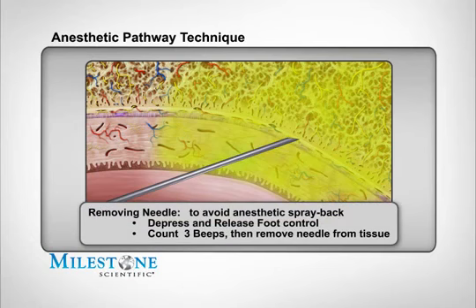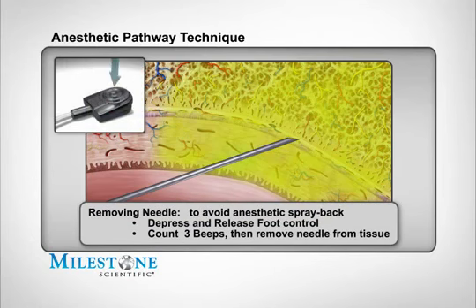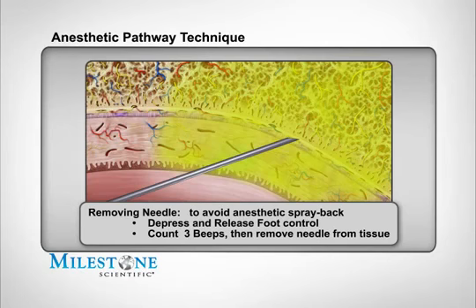To avoid anesthetic solution spray back into the patient's mouth, perform the following: depress and release the foot control pedal, count 3 beeps after releasing the foot control, and then remove the needle from within the patient's mouth. Direct the needle away from the patient, as a small amount of anesthetic solution may still be present.